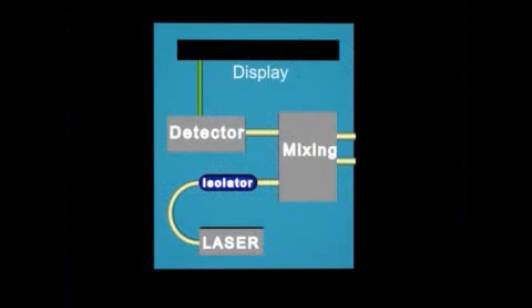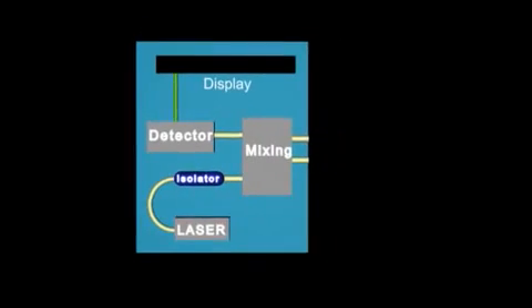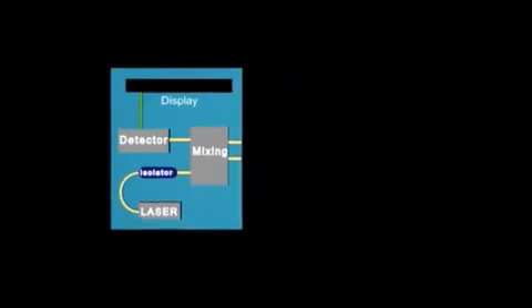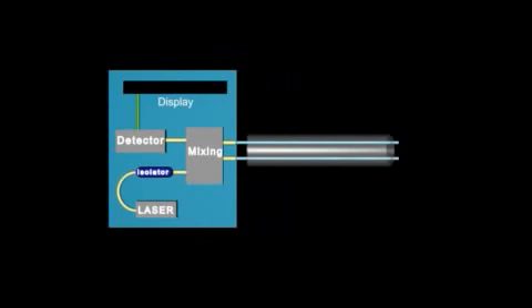This graphic shows how the AFSID system works. Light from a laser source operating at 1550 nanometers passes through an optical isolator, through an optical mixing and signal management module, to the optical ports on the rear of the instrument. Using optical jumpers, these ports are terminated to a pair of spare fibers in the cable to be located, and a loopback jumper or connector is applied to the fibers at the remote end of the cable span under test.